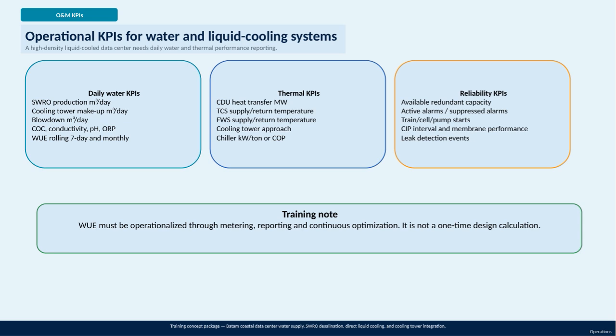Reliability KPIs include assessing the available redundant capacity to ensure system resilience, monitoring active and suppressed alarms, counting the number of starts for trains, cells, and pumps, tracking the cleaning in-place intervals and membrane performance for the desalination system, and recording any leak detection events.